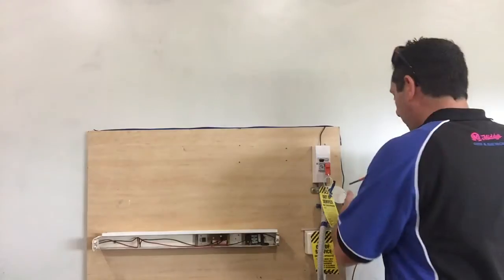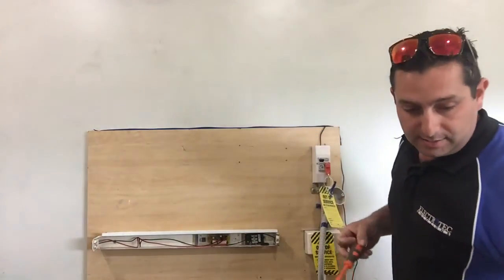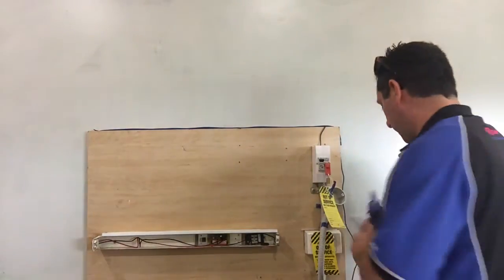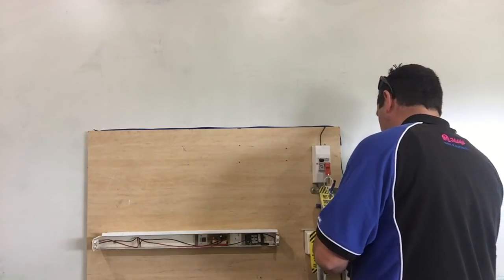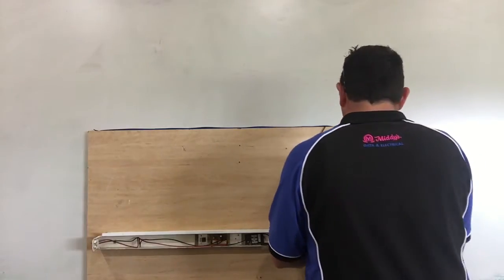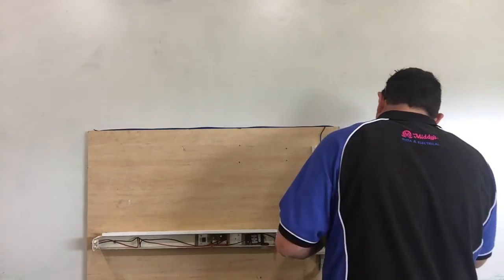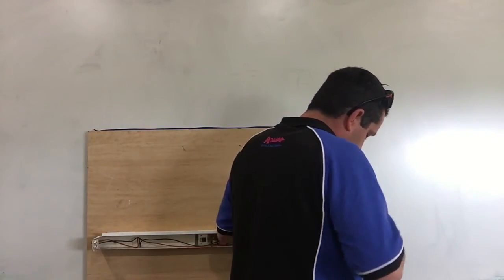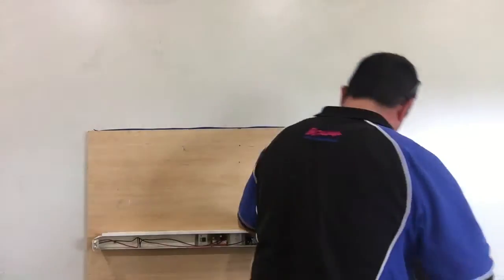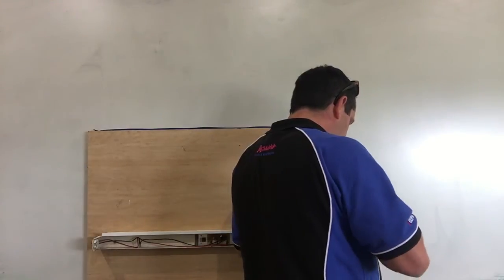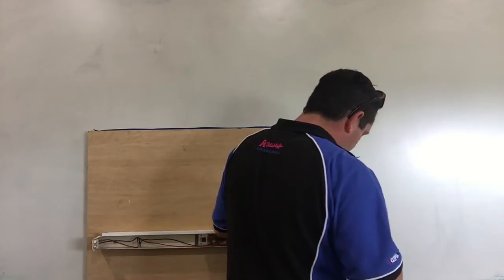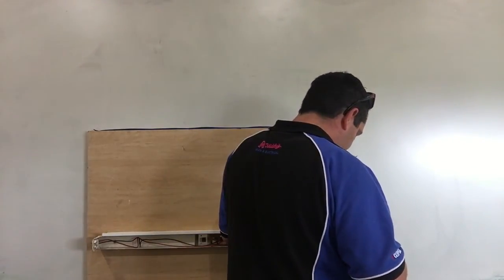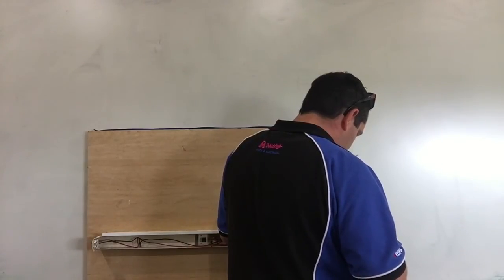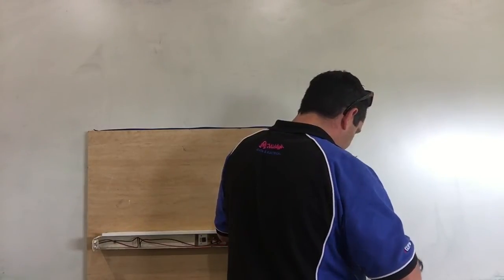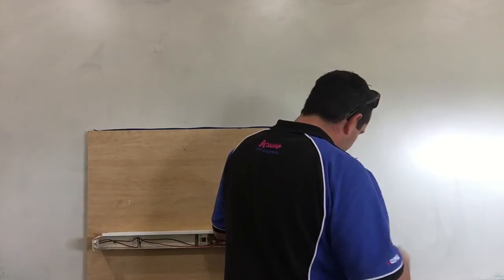Next, we're going to open up our junction box. We're going to test that our conductors are still dead. Test our tester, active, neutral, active earth, neutral earth. And then from our known earth, we're going to test each conductor. So we're going to go from our known earth, we're going to unwrap and test our active. Unwrap, test our earth. Unwrap, test our neutral. And then we're going to test between each other.